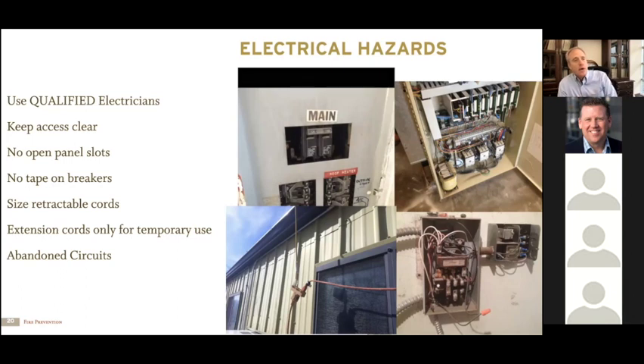holes, not only could someone possibly get their hand inside there and touch a live electrical bus or wires, it's also where a spark could come out from that panel if there's something coming into contact with those wiring back in there. And of course, having those open slots into that panel can also allow dirt and dust and other things to get inside there that could also result in igniting a fire, introducing a fuel back in there around those live wires.